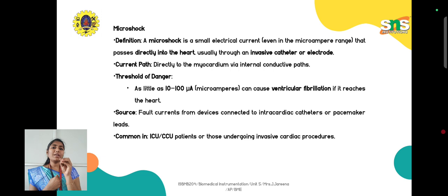Since it makes direct contact with the organ, there is a very high chance for the shock to directly affect the organ. So even a very minute leakage current is good enough to produce the shock. So that is the thing here.